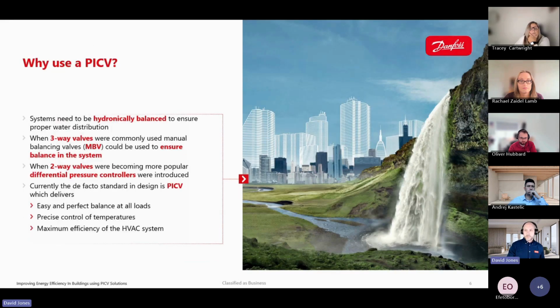So why should we consider using pressure-independent control valves, or PICVs? In order to answer this, we have to look back at how systems were balanced in the past. As system design has evolved, so has the way we achieve hydronic balance. In traditional constant flow systems, three-way control valves were commonly used. Because flow through the branch remained relatively stable, manual balancing valves could be set during commissioning to proportionally distribute flow. Once set correctly, the system behavior was reasonably predictable.